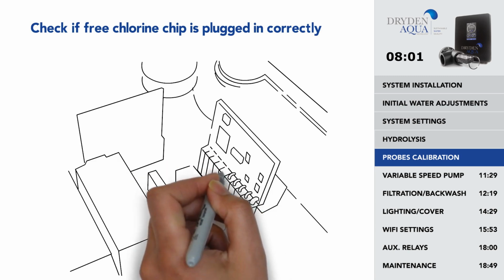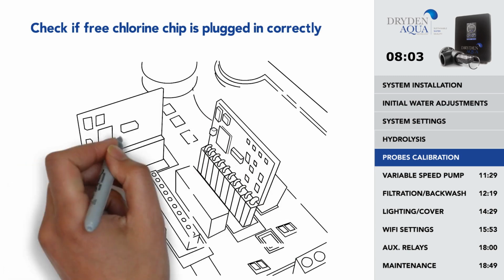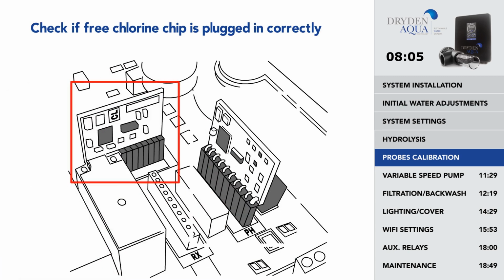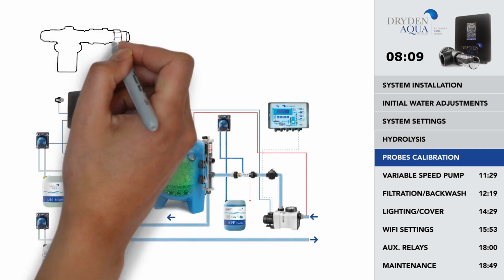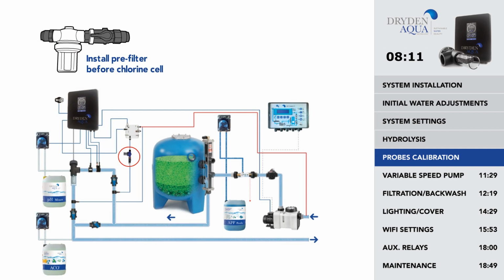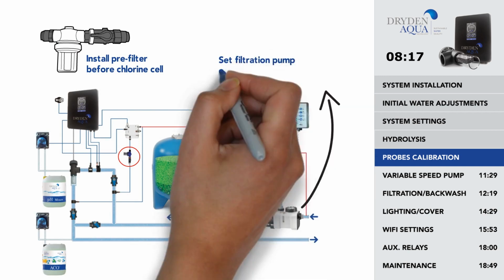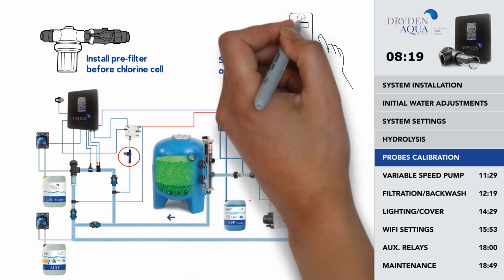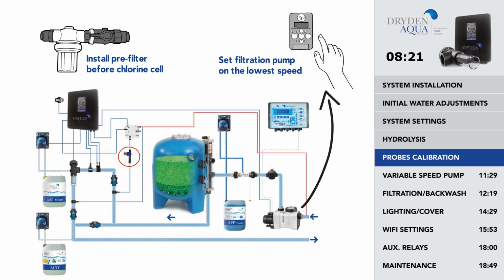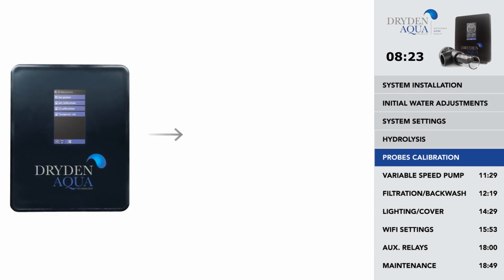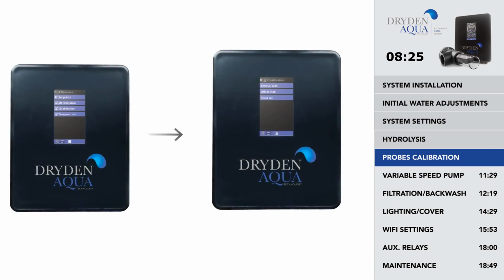Once the probe is connected, check if the free chlorine chip is plugged in correctly and make sure the green LED light is blinking. You may now install the pre-filter before the free chlorine cell. Also, in case you are using a variable speed pump, it is important to set your pump on the lowest filtration speed, speed 1, before starting the calibration. It is recommended to calibrate the free chlorine probe every 2 to 3 months.